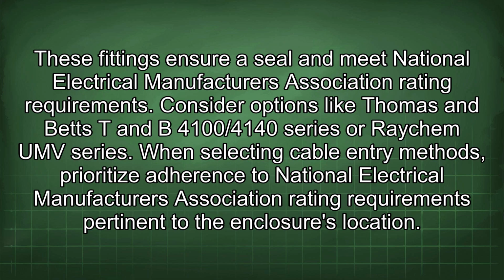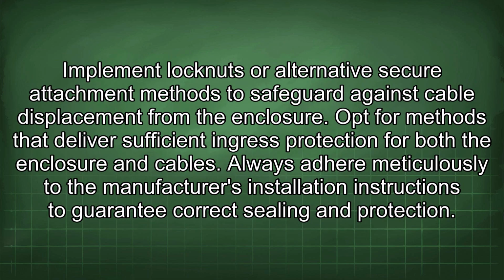When selecting cable entry methods, prioritize adherence to National Electrical Manufacturers Association rating requirements pertinent to the enclosure's location. Implement lock nuts or alternative secure attachment methods to safeguard against cable displacement from the enclosure. Opt for methods that deliver sufficient ingress protection for both the enclosure and cables. Always adhere meticulously to the manufacturer's installation instructions to guarantee correct sealing and protection.